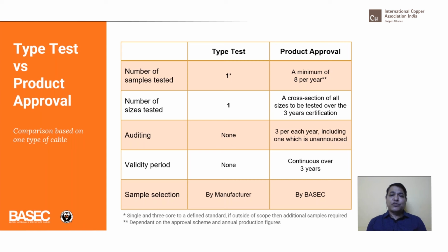In case of type test, one sample is tested, and when it comes to product approval, we test minimum 8, which is 16 for a new customer, but for a customer who is consistently performing good quality throughout our audits, it is 8 per year. The number of sizes tested in the type test, they normally choose either the biggest one or a middle size between the biggest and smallest sizes. But when it comes to product approval, all of the sizes are randomly taken. It is not only minimum and maximum.